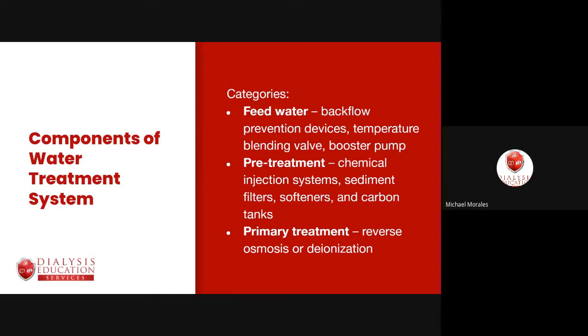Primary treatment is the reverse osmosis membrane — a mechanical method of filtering water under high pressure, forcing it from an area of high concentration to lower concentration across a very small submicron filter. It is a thorough treatment that removes sediment, chemicals, and down to viruses. Deionization is usually used as a backup.